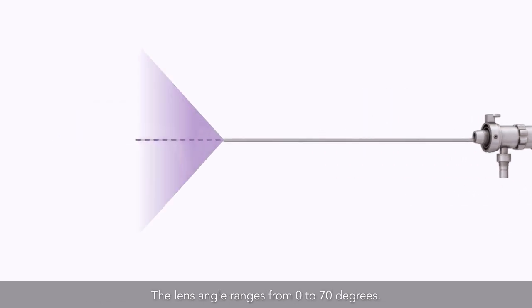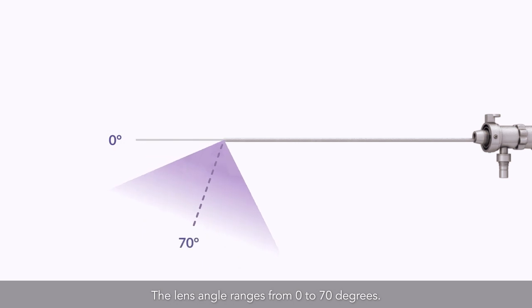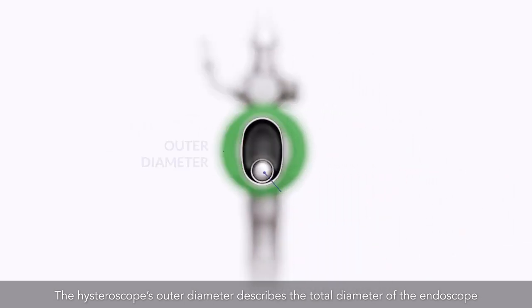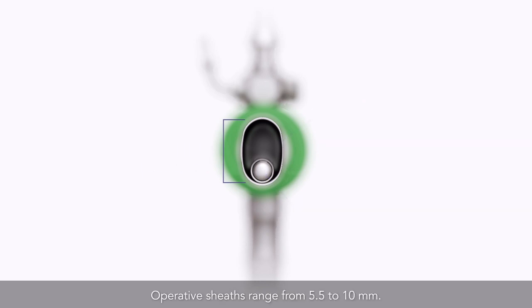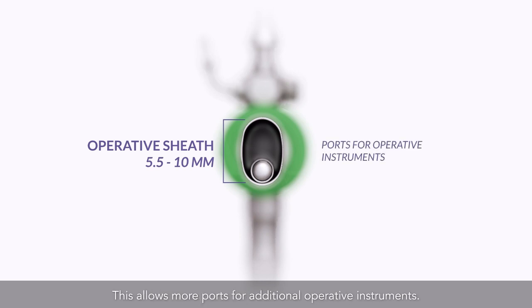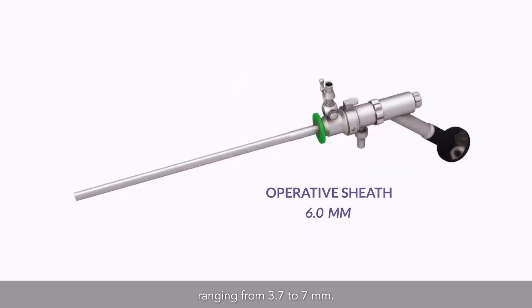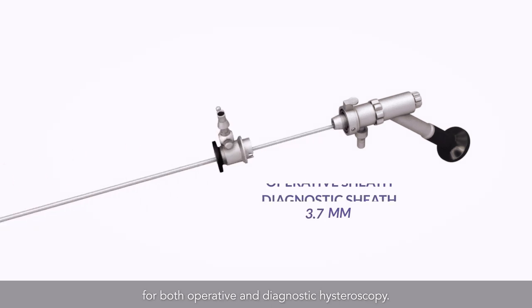The lens angle ranges from 0 to 70 degrees. The hysteroscope's outer diameter describes the total diameter of the endoscope plus outer sheath. Operative sheaths range from 5.5 to 10 mm, allowing more ports for additional operative instruments. Diagnostic sheaths are smaller in diameter, ranging from 3.7 to 7 mm. Some hysteroscopes are able to accommodate a range of sheath sizes for both operative and diagnostic hysteroscopy.